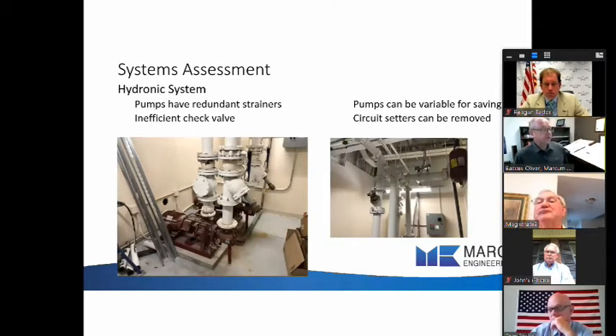The next system that I assessed was your hydronic system. That is HVAC water that loops through the building that all units exchange heat with. The pumps noted have redundant strainers. In this picture, you'll see there's two types of strainers in series. That's just excessive pressure drop. I would recommend removing one of those. The pumps could be variable for savings. These are constant volume pumps. At 10 horsepower running all day long, that's a lot of kilowatts.